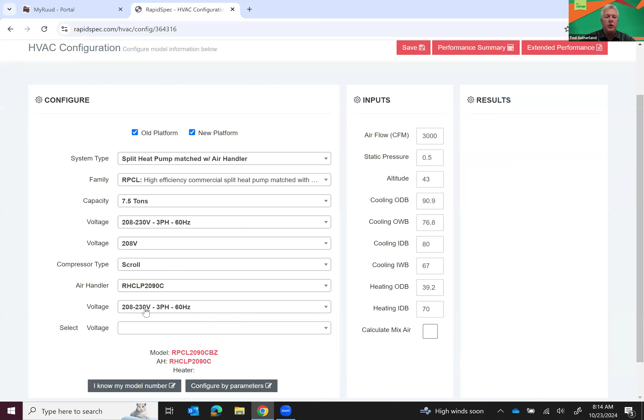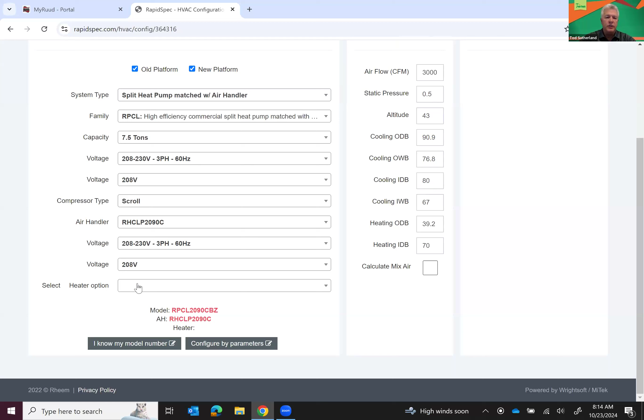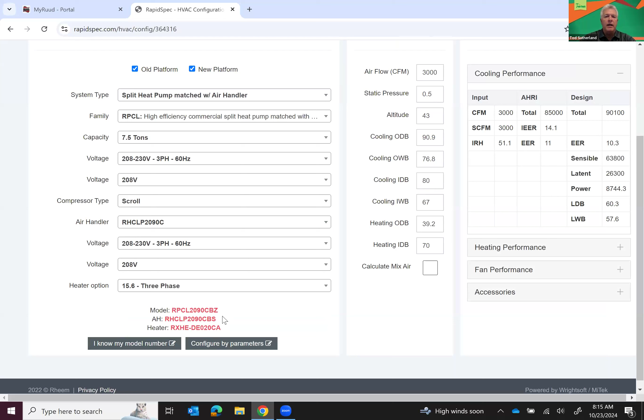Now, the reason it's doing that is because we need to know specifically, is it 208 volt or 230 volt? Because that's going to make a difference on the heat strip that we select. If we select a 10 kW heat strip at 230 volt and we apply it to a 208 volt application, it's going to be less than 10 kW voltage or wattage. So we'll come down here, we'll select this 15 kW three-phase, and notice it's populating the model numbers at the bottom here as we go.